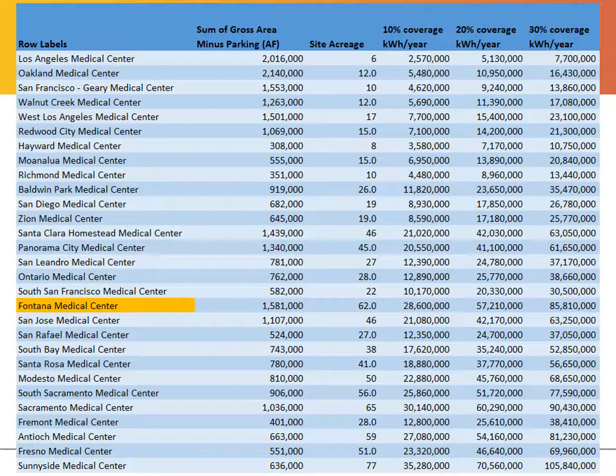One thing we have is a big portfolio full of buildings, and we looked at that portfolio because we have all the data. What we could say is that if you cover 10% to 25% of a hospital's site in solar panels, then to zero out the energy, you'd need to get your consumption down to between about 40 and 110 kBTU per square foot per year for net zero. The number I've picked is right in the middle of that. I like to say the target for a net zero hospital is 65 kBTU per square foot per year. That's what I call the net zero target.